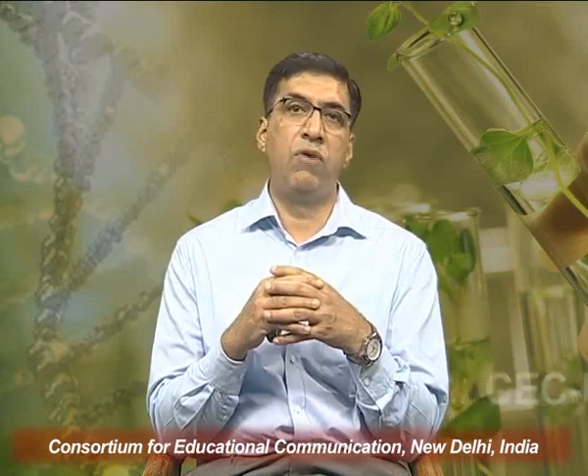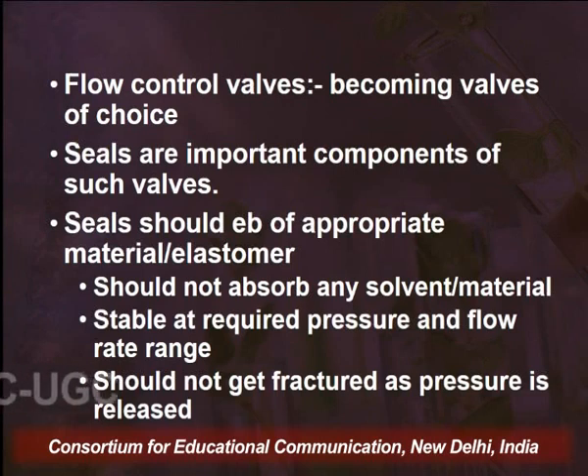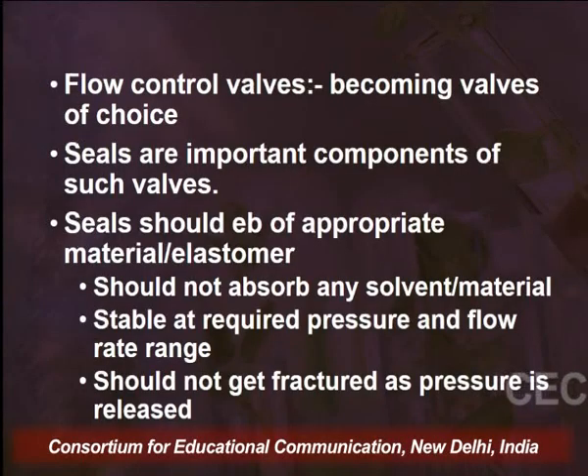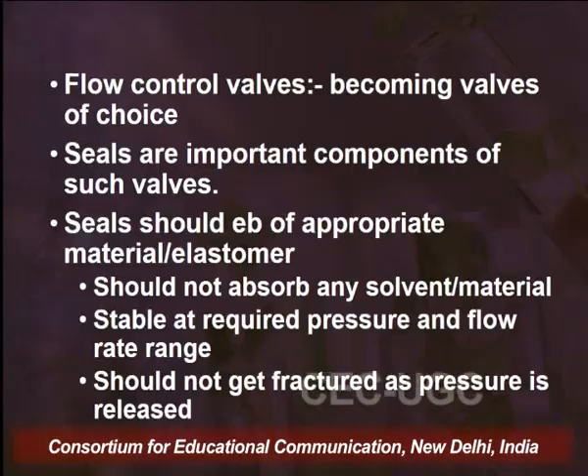Whereas the flow control valves are now becoming valves of choice in the supercritical fluid extraction industry, because with these valves you can control the flow rate and also you can stop the flow. And the seals that are used in these control valves form an important component, and therefore whatever material we are using for the seals of these valves, it should not absorb any kind of solvent or solute.